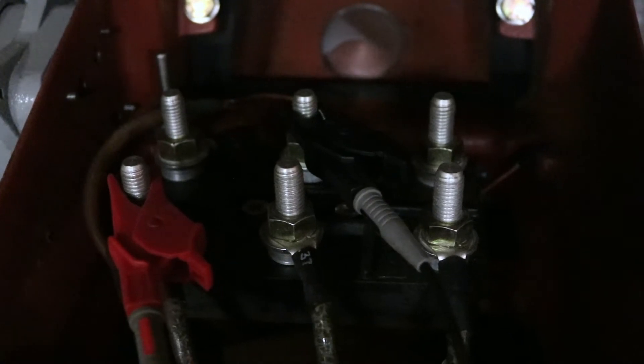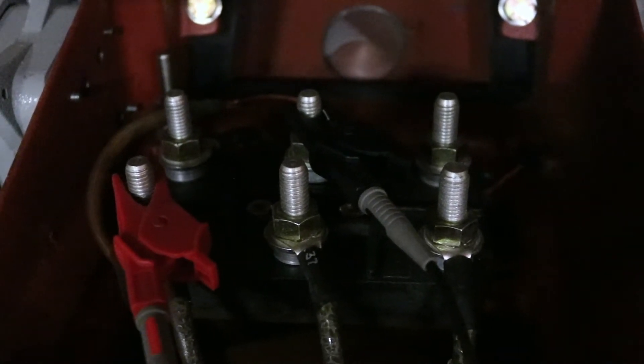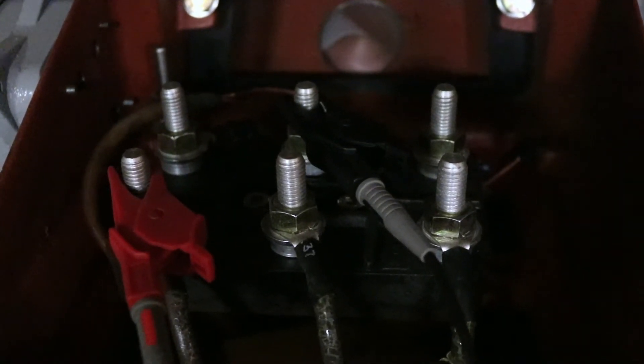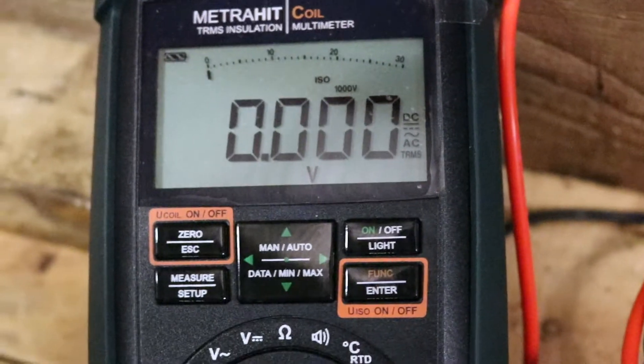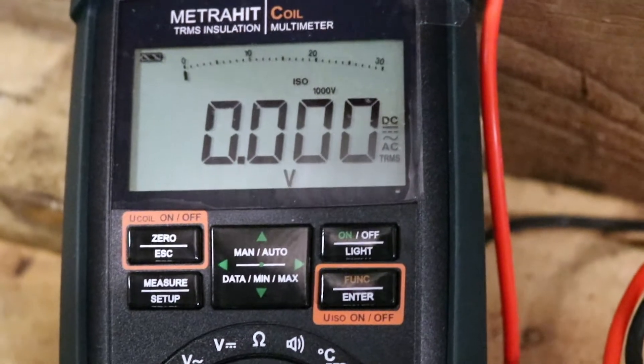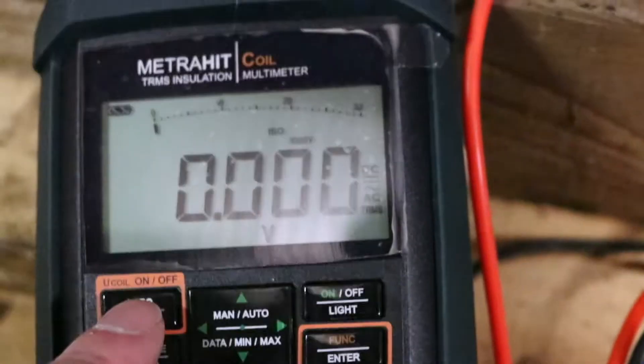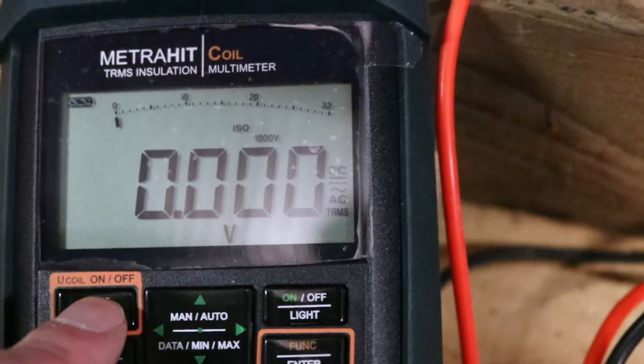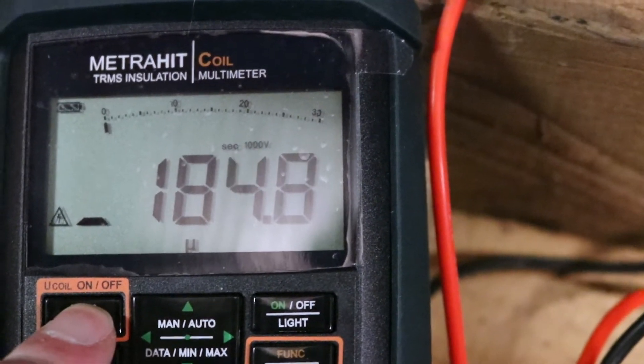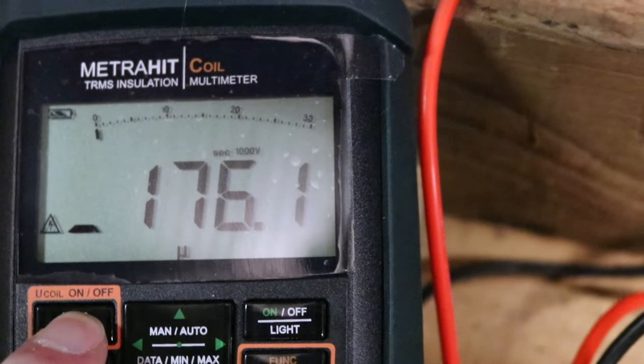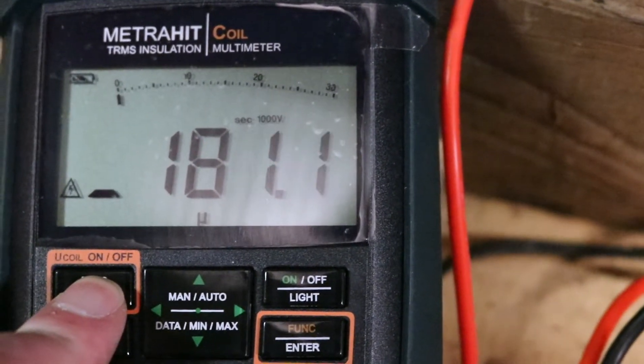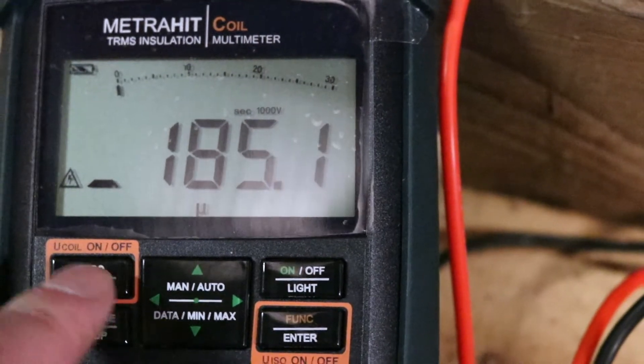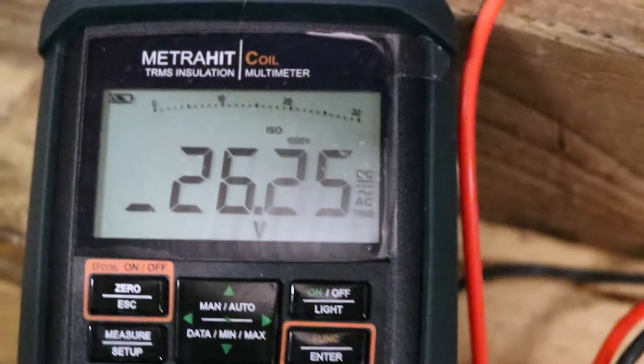We've now set things back up and we've taken out the shorting straps. And we are now just windings on their own, connected up for the U winding for the first test. Now we're filming. And we've done all winding checks. They've all got resistance. Stopped jumping about on the U phase there.